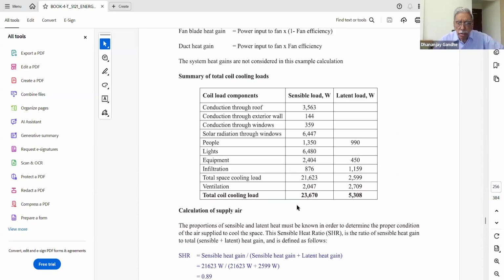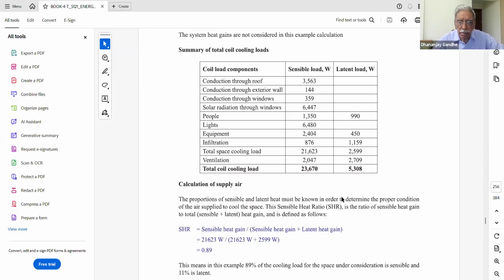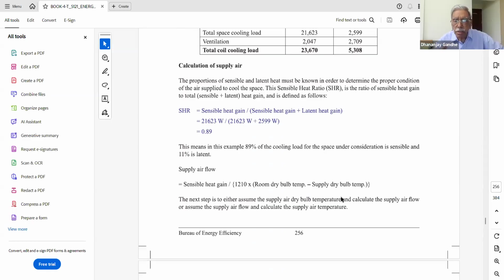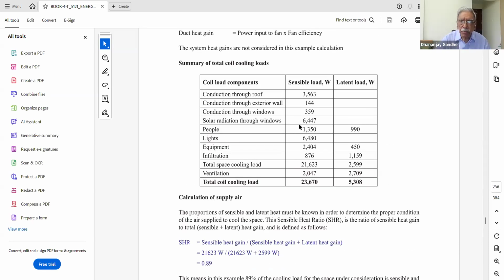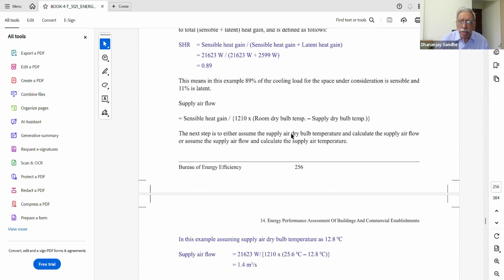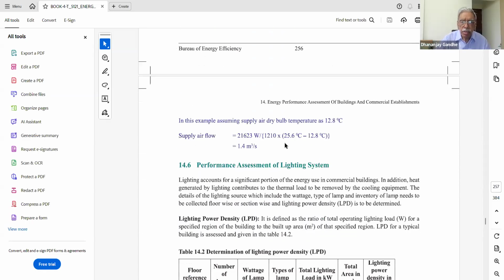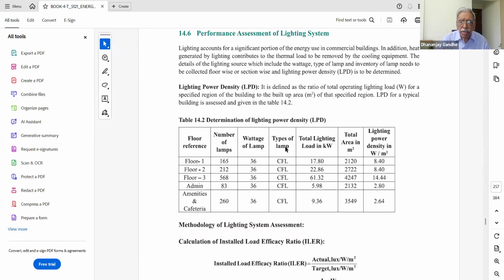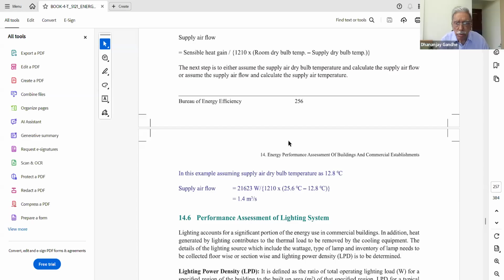So the total load, the cooling coil load, how much air conditioning system load will come on the system, is a sensible heat of 23,670 and a latent heat load of 5,308. Okay. Similarly, for supply air, ventilation is basically for the supply air to be replaced at intervals. The heating load for supply air is calculated in a similar manner, and the total of the summary is calculated.